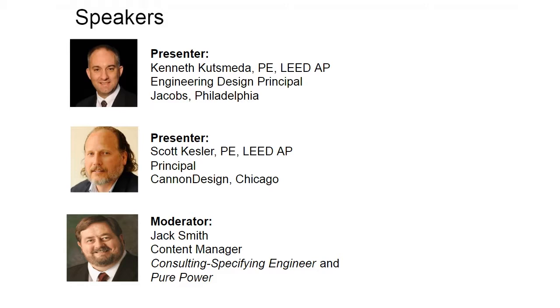So we're still seeing a lot of diesel on the data center side just because of the reliability. But as emissions become more and more important, we start to see natural gas. There are some combo generators that will use diesel to start and then move to natural gas, so that's an option. Those systems are relatively small right now. They are getting larger, but we don't see them in data centers as much. Maybe some of the smaller sites that don't have a big impact, just because of the fuel source. So it all really depends, but those are probably the main differences that I would see.